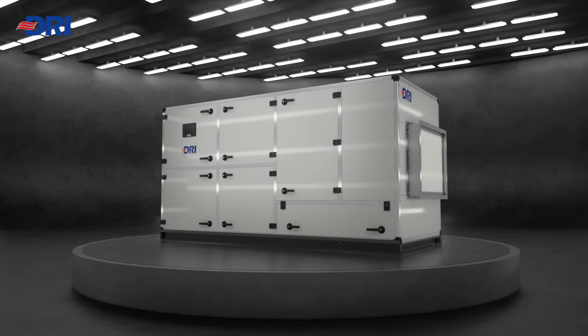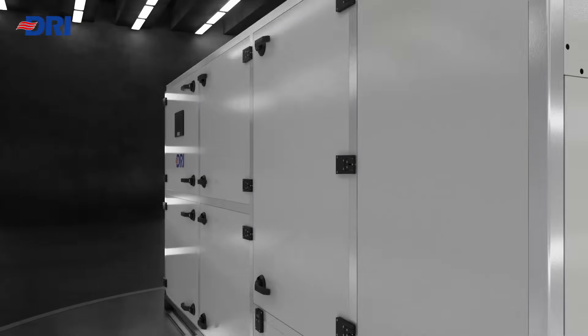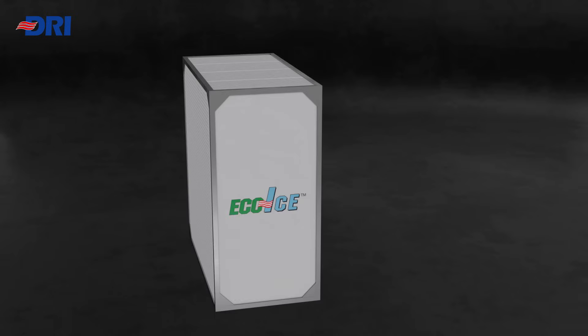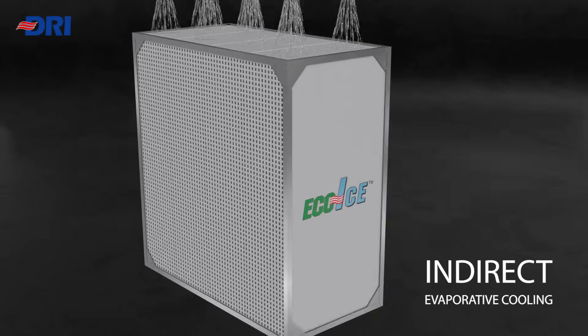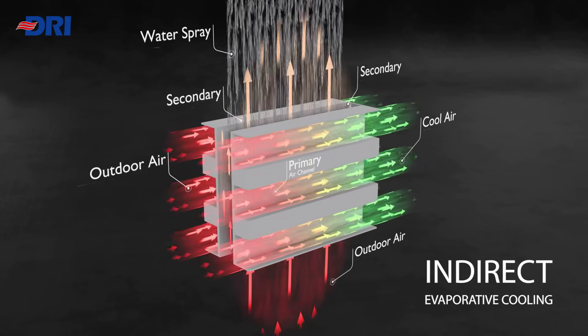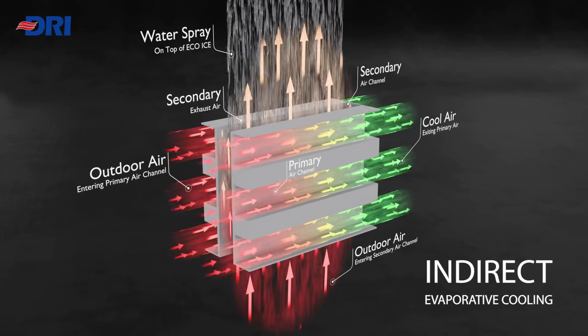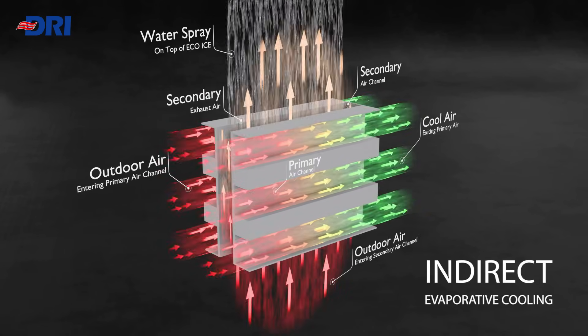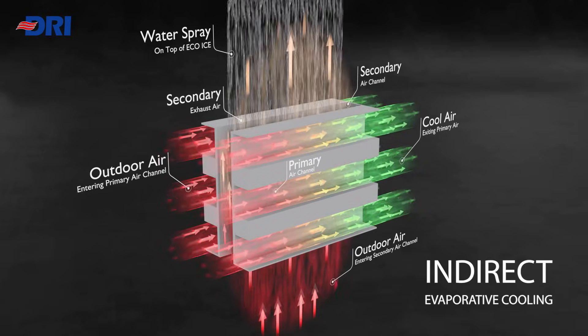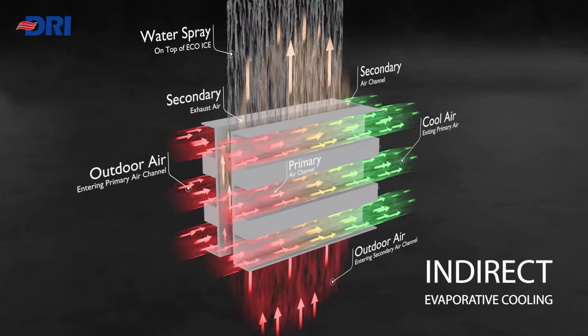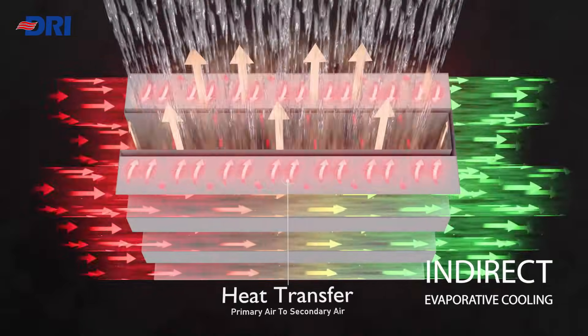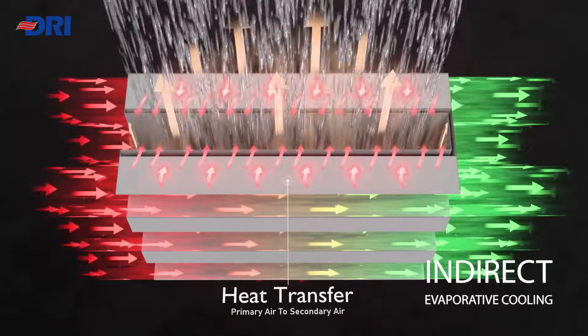Let's explore its innovative mechanism. The cooling process begins with indirect evaporative cooling. Warm, dry outside air is drawn into the IDEC unit. Inside the high-efficiency eco-ice core, this air is divided into primary and secondary streams. Both air streams run in separate dry and wet channels in the heat exchanger. The secondary stream is moistened and used to cool the dry stream of air through the heat exchanger, which facilitates the heat transfer from primary air to secondary air.